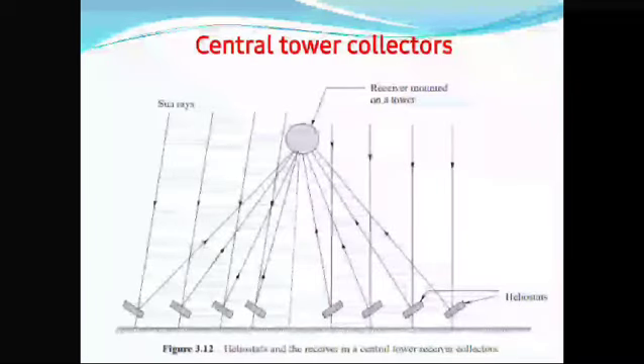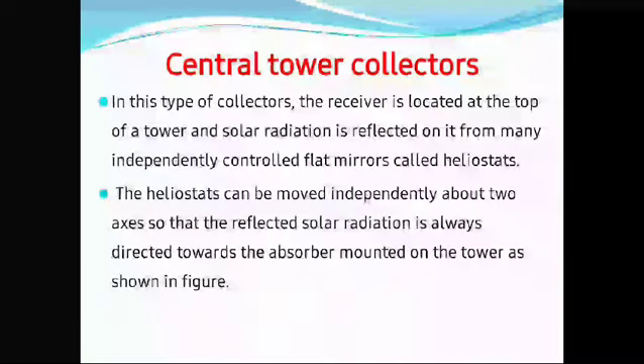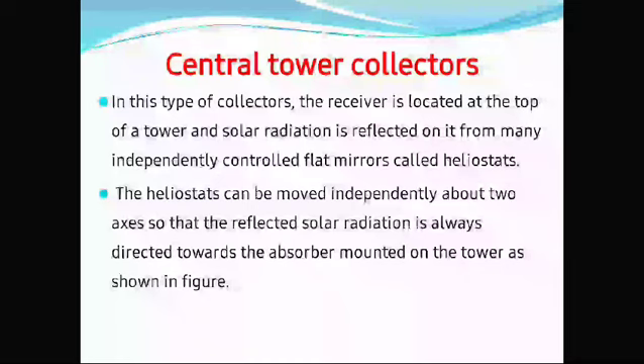The last type is the central tower collector. In this type, the receiver is located at the top of a tower and solar radiation is reflected onto it from many independently controlled flat mirrors called heliostats. The heliostats can be moved independently about two axes so that the reflected solar radiation is always directed towards the absorber mounted on the tower, as shown in the figure.